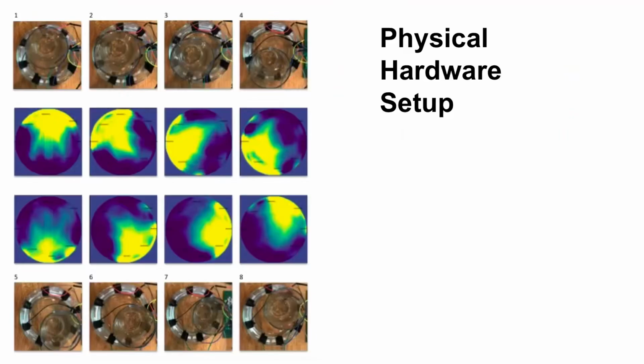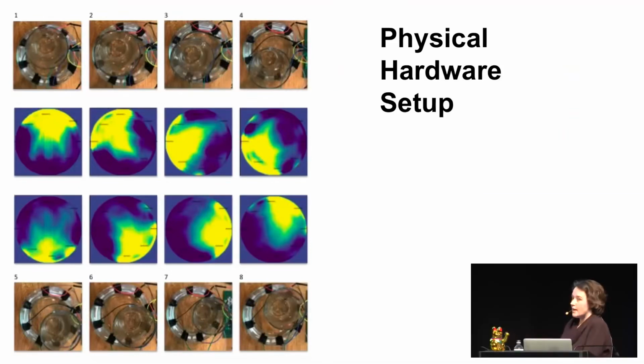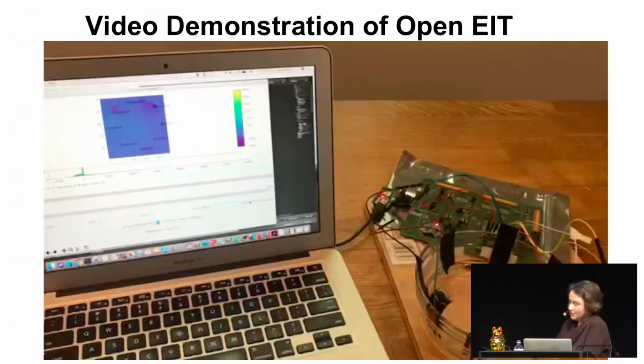This is what it looks like when you reconstruct something. I have a phantom up there, which is a pot of water with a cup in it, and I move the cup around anti-clockwise. So you can see in each of the pictures I move it around a little bit more, and you can see the reconstruction there with me moving the cup around. Again, this might not be wowing you with the resolution at only 8 electrodes. It's a proof of concept, but that's okay.